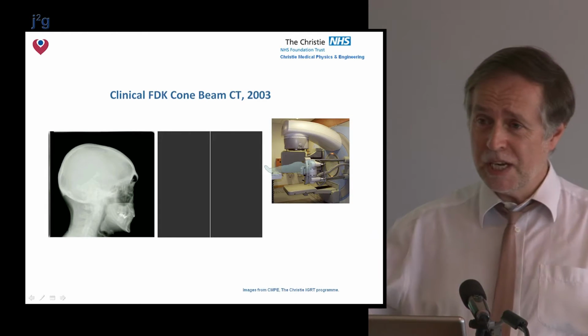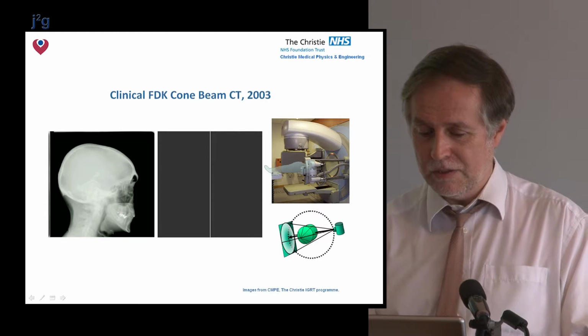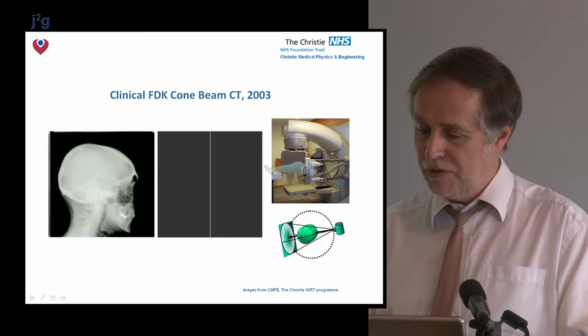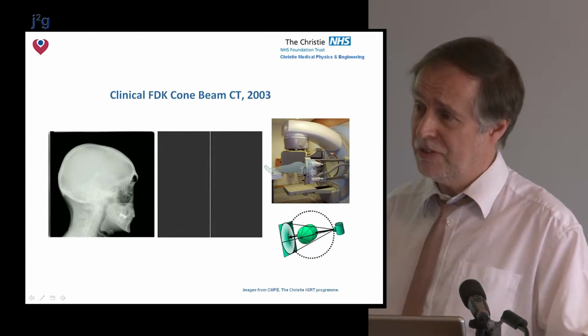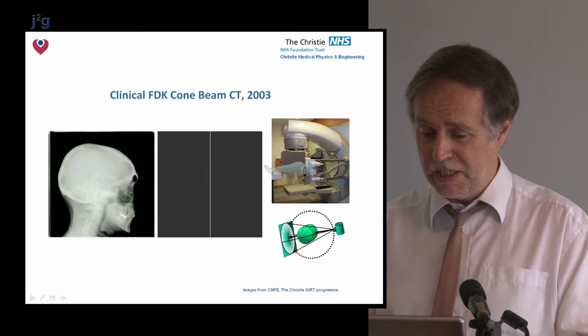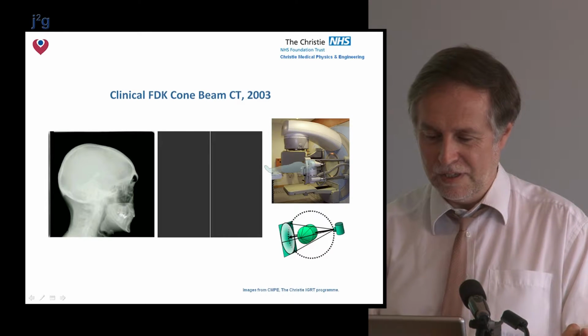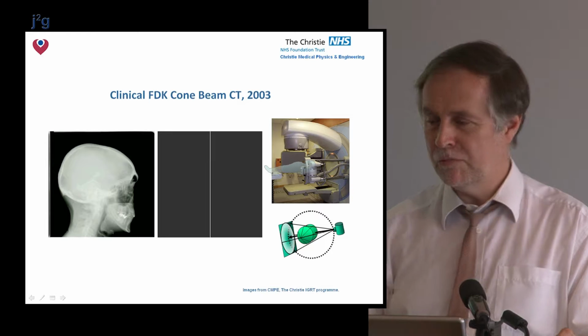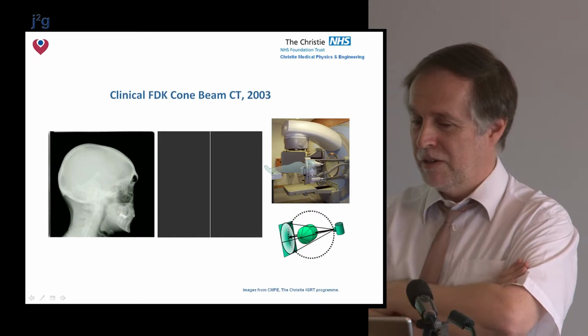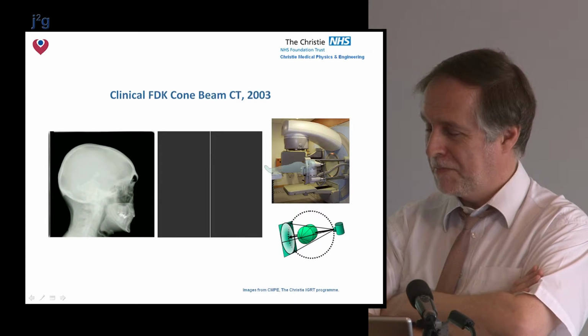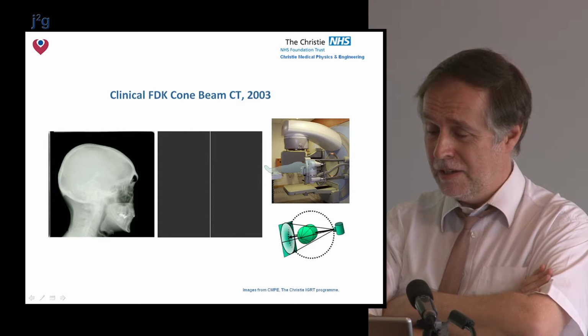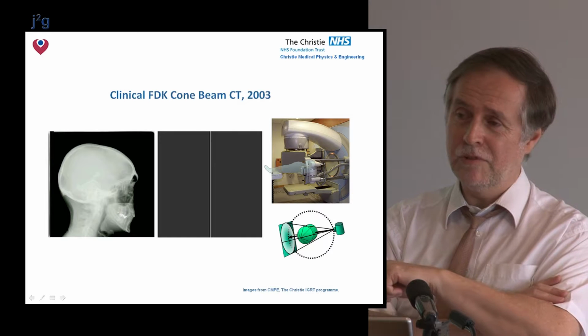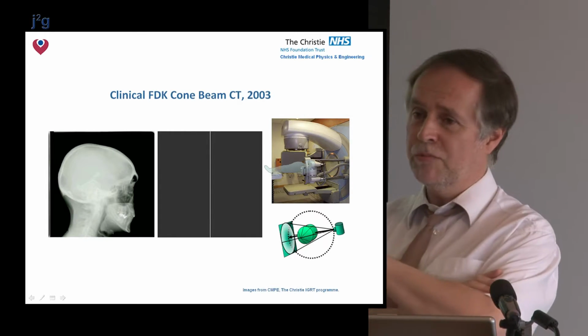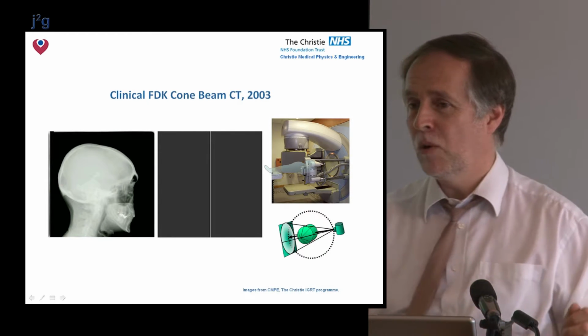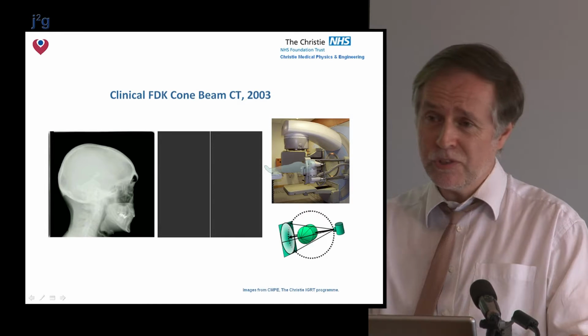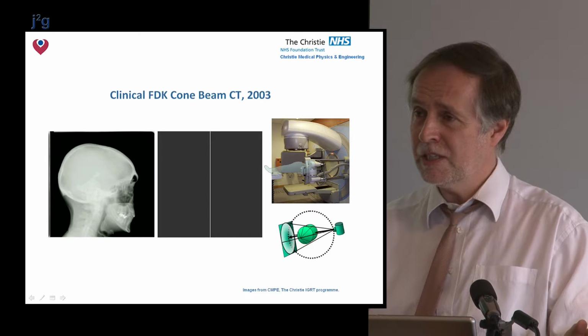Cone beam CT imaging is where you keep the X-ray fluoroscopic pictures on, and you can see in this particular patient we're rotating the X-ray unit around the patient. Don't forget this X-ray unit is actually attached to the linear accelerator gantry, so it's got the same mechanism for moving. So we've rotated the gantry around the patient, and we've taken the fluoroscopic sequence here, and then we can reconstruct an image literally in one ear, through the head, and out the other ear. And what that did overnight in 2003 is propel radiotherapy ahead of radiology, because we were able to see in the treatment position a patient with 1 millimetre accuracy in all directions. So we could have 1,000 by 1,000 by 1,000 points of our patient in exquisite detail at the point of treatment.